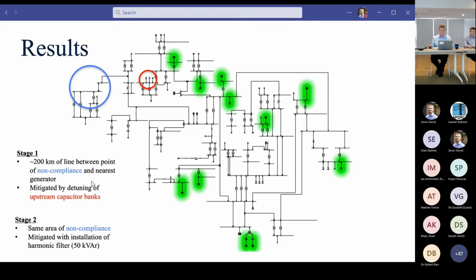And what we find is that all we need is a 50 kVAR filter at that point, connected directly to that point of non-compliance. Now, if we compare that filter size to what we're seeing being connected directly to PCCs of generators at the moment, we're seeing filters that are 10, 20% the size of the nominal power of the generator itself, even to the point where the generator is no longer able to meet its reactive power capability. So the relative size, when we start talking about tens of kVARs, is substantially lower.